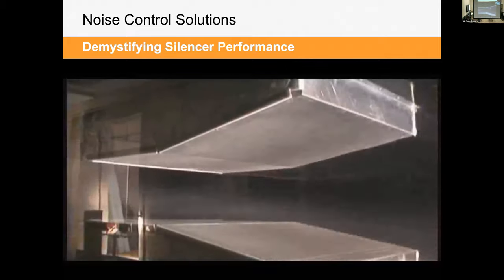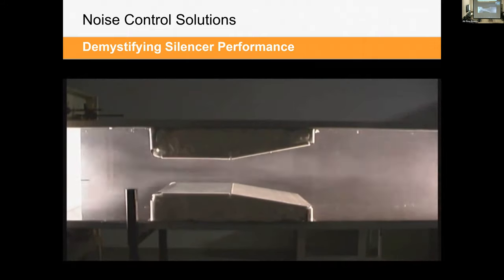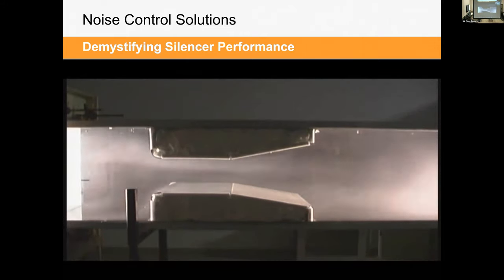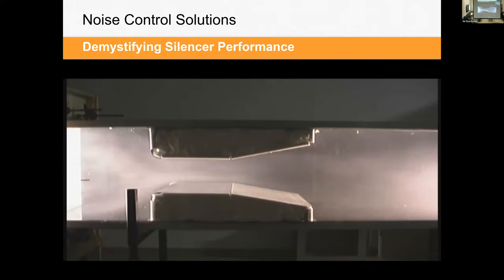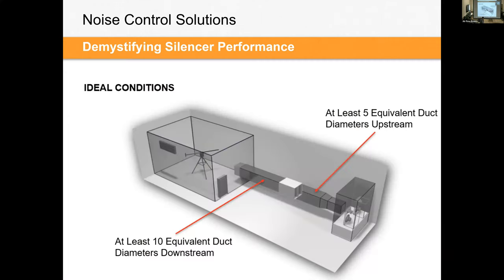And this smoke demo actually shows you why we have a radius inlet. You can see that laminar flow developing, and then this tail section where you get that static regain. This wasn't by accident. We spent a lot of time and effort doing CFD and building samples and checking angles and radiuses to really optimize the construction of these things. It seems kind of crazy, silencers are pretty simple. They've been done for 50, 60 years, but we wanted to optimize all of these different variables to the best extent possible to make sure we had the best performing silencer.